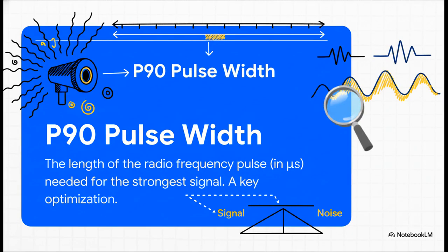Another key piece of the puzzle is the P90 pulse width. Think of it like this: to get a signal, the machine basically shouts at the sample with a radio pulse. The P90 is the perfect length for that shout, not too short, not too long, to get the loudest possible echo back from the sample. Getting that timing just right, down to the microsecond, is absolutely crucial for getting the best possible signal-to-noise ratio.